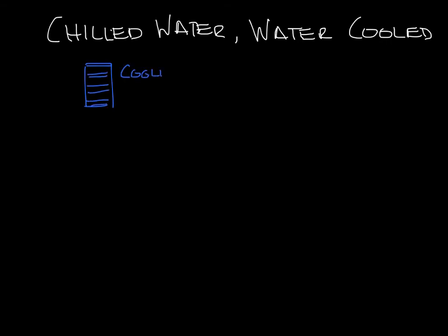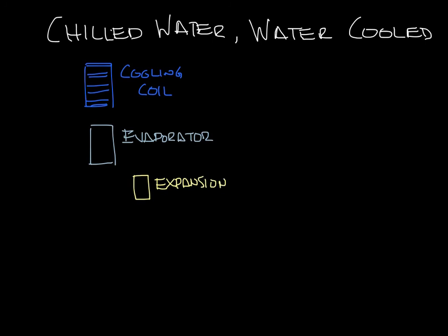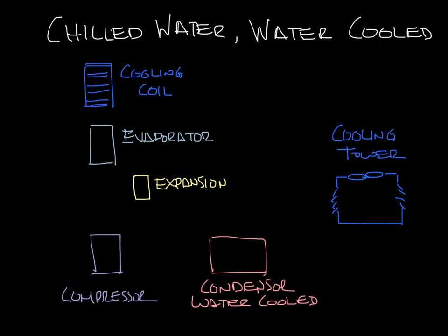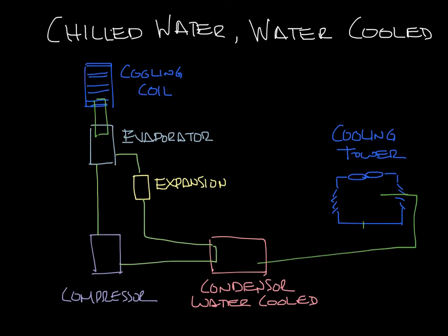We have our cooling coil, our evaporator, our expansion device, the compressor, and the condenser, which is water-cooled, and our cooling tower. So now you have the loop going from the evaporator to the compressor to the condenser to the expansion device and back to the evaporator, plus a chilled-water loop that goes from the cooling coil to the evaporator, plus the loop that goes from the cooling tower to the water-cooled condenser.